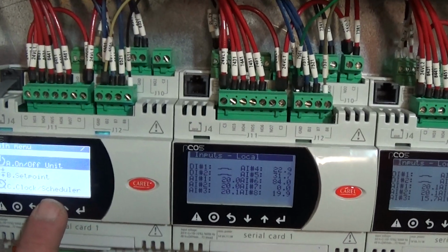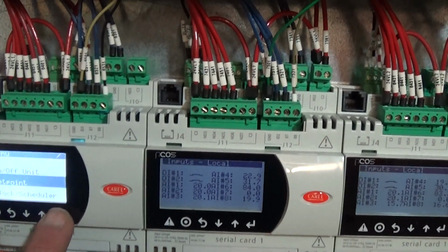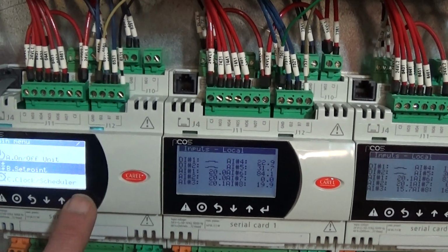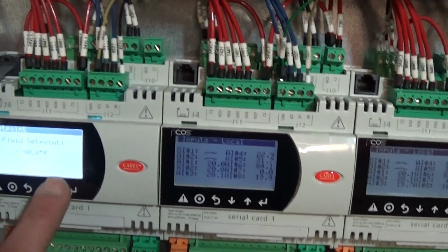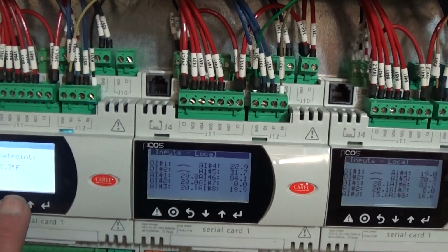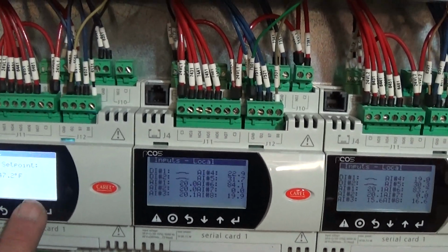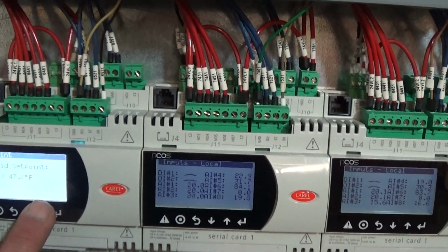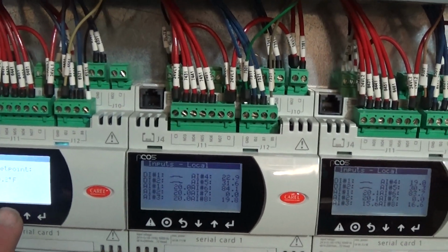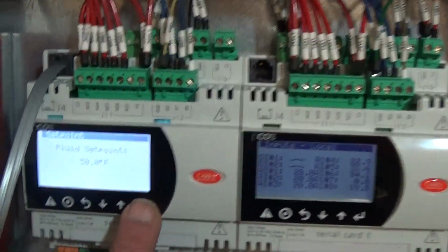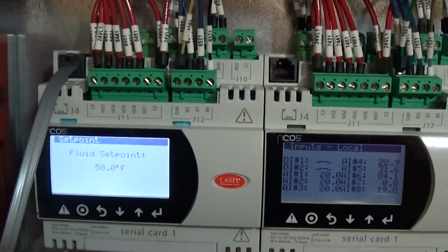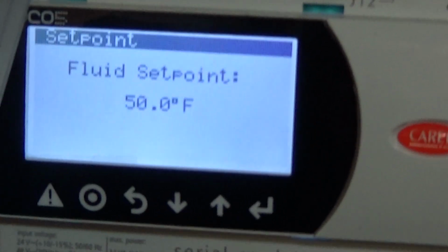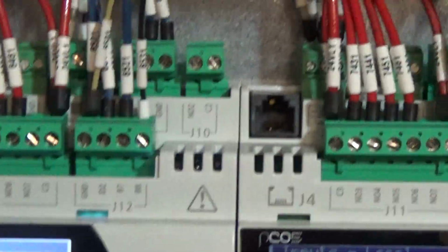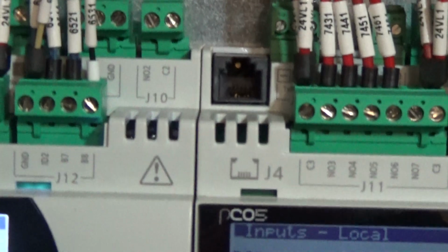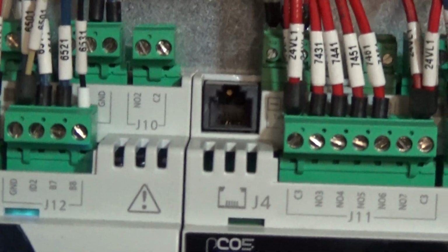So we scroll down in the main menu to B, set points, enter, enter again, and then we're going to use the down button to go down to about 50 for a set point. There's our 50. And then we hit enter again. And that starts the first compressor. Now, in all of this, to escape from that set point screen, we're going to hit that back button. And we're back into set points.